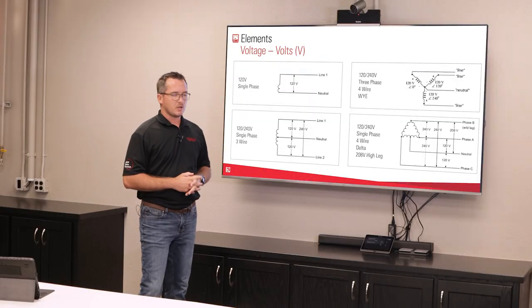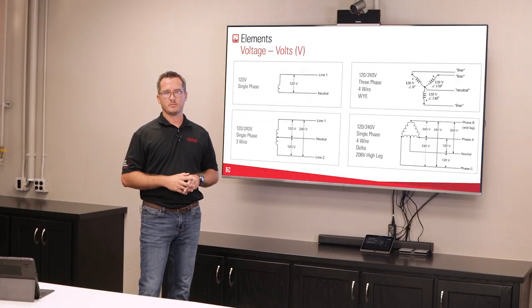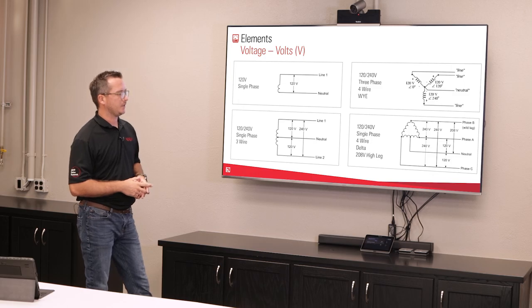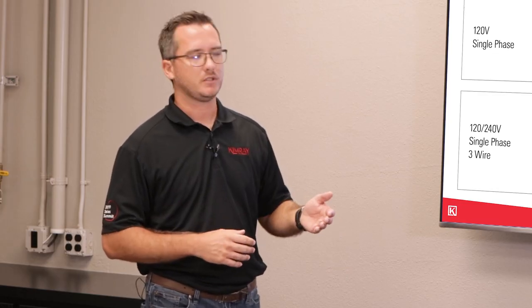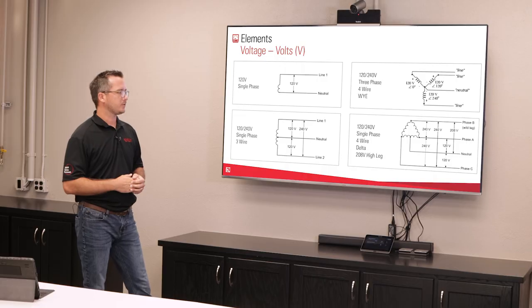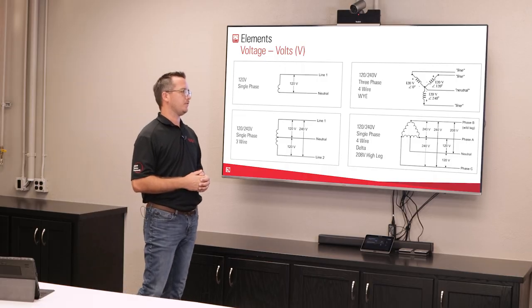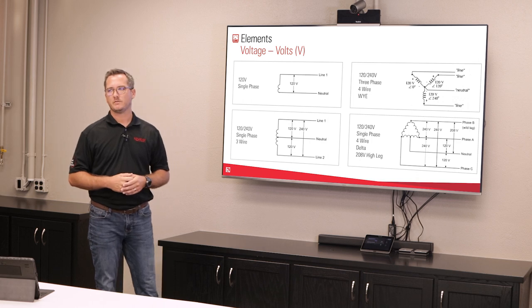So there's 120 volts and 240 volts, but you can wire your system to get comparable voltage. Instead of 120 doubled to 240, you can also cut it to 208. That's where you're going to see a lot of your equipment out in the field, depending on where it's manufactured.